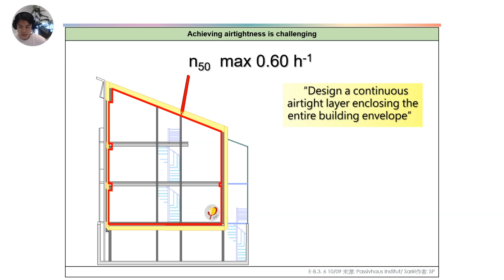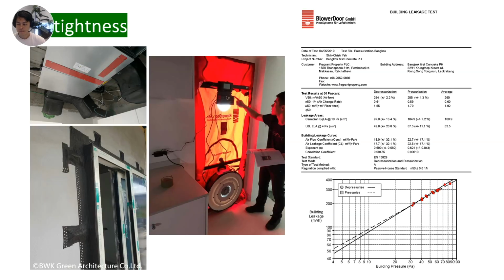So in this project we invest in a high efficiency ERV system. It is essential to also improve the airtightness of the building. Otherwise, the performance of such an efficient machine becomes almost meaningless. We choose a high efficiency ERV system, so at the same time, we need to improve airtightness. As mentioned above, the design of the MVHR and the airtightness of the building envelope also become important, especially when we consider a mechanical ventilation system. Unregulated ventilation should be decreased.